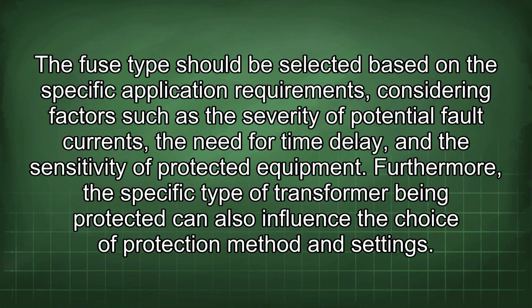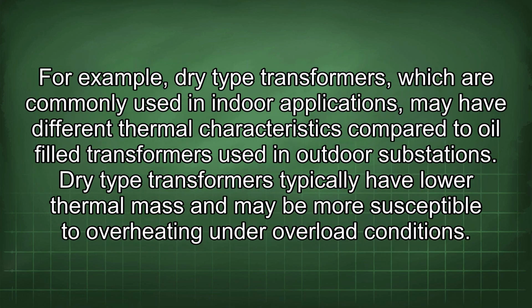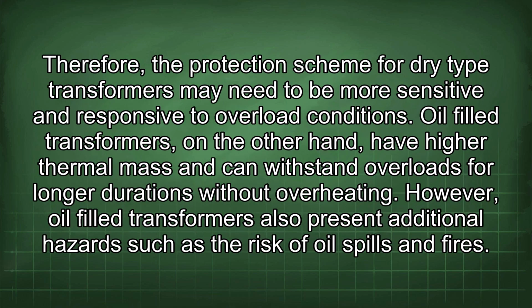Furthermore, the specific type of transformer being protected can also influence the choice of protection method and settings. For example, dry-type transformers, which are commonly used in indoor applications, may have different thermal characteristics compared to oil-filled transformers used in outdoor substations. Dry-type transformers typically have lower thermal mass and may be more susceptible to overheating under overload conditions. Therefore, the protection scheme for dry-type transformers may need to be more sensitive and responsive to overload conditions.